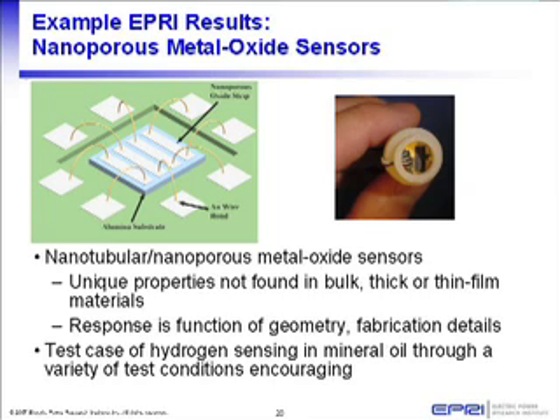Now just for a few examples - and these are just a very few sets of examples. I chose this first one because it's a new sensor. Sensors have to monitor not only the equipment but also the grid so operators can control it better. This particular sensor is designed to monitor gases dissolved in the dielectric fluids of transformers.